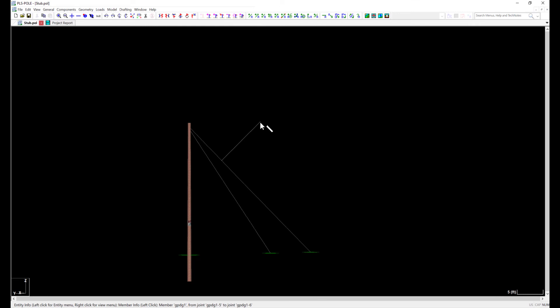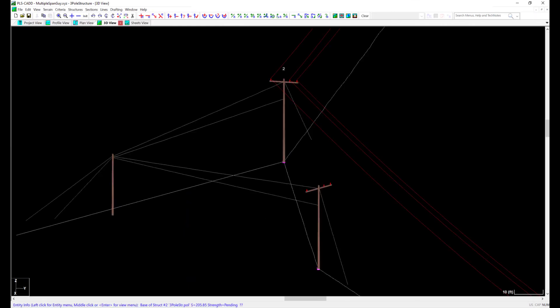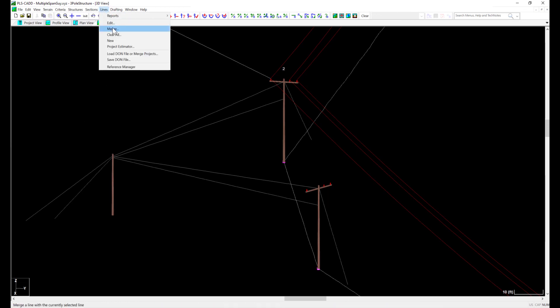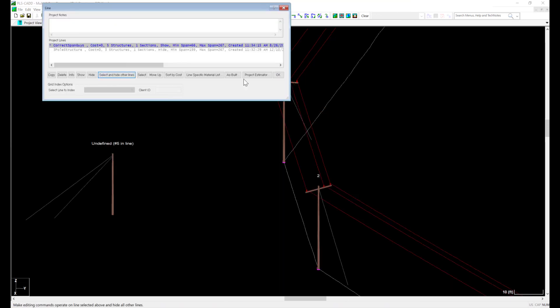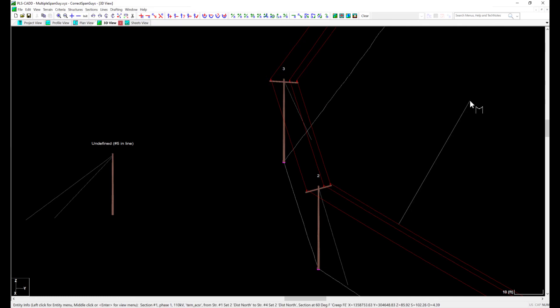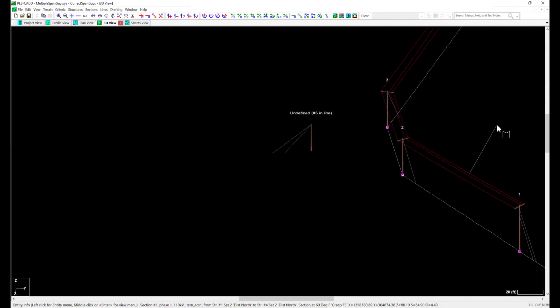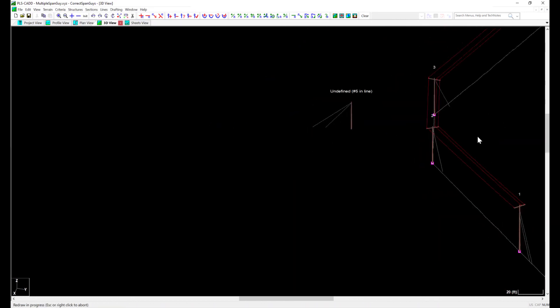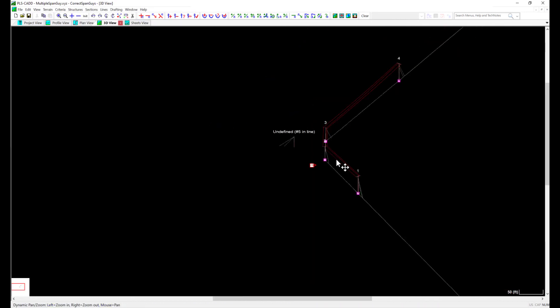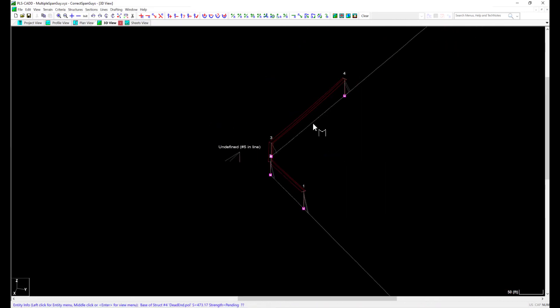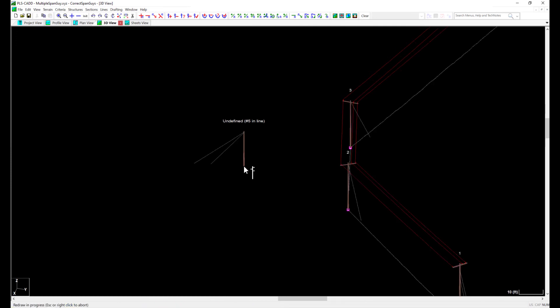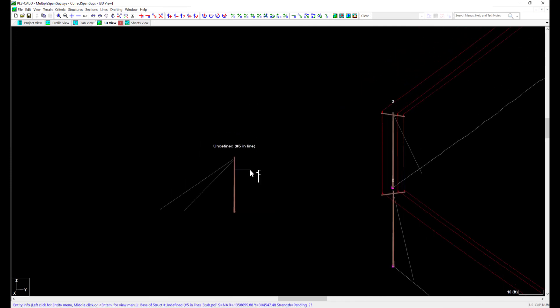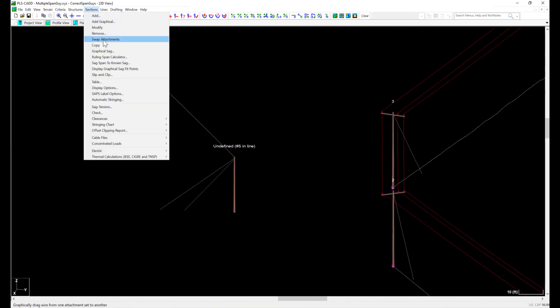At this point, I have everything I need to complete this model. Instead of removing my previous work from the PLS-CADD model, I'll go to Lines, Edit, and select a line layer that has my dead ends and all structures with wires strung to both structures. Now, the only part I'm missing is my span guys between the structures. To add this, I'll use the sections add graphical command.